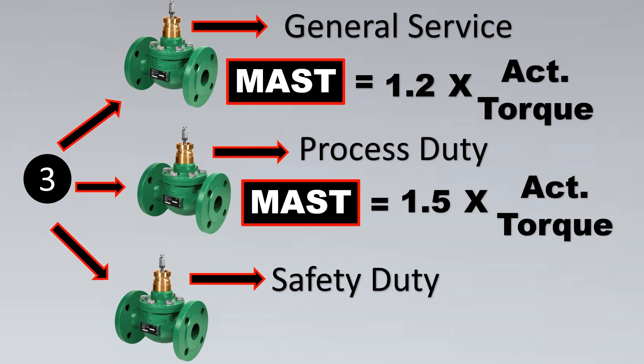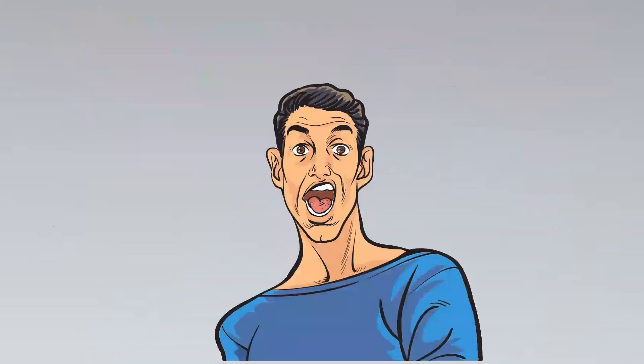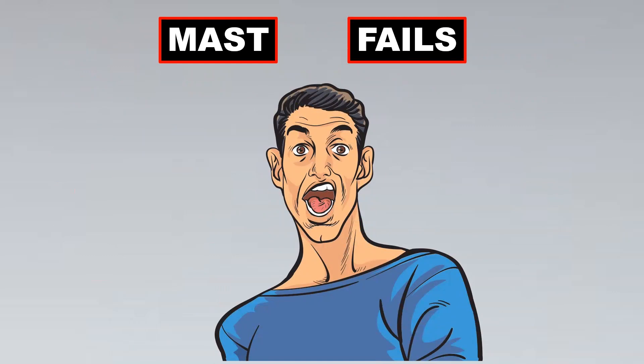When the valve is for safety duty applications — like shutting down the plant or preventing liquid escape — MAST should be equal to 2 times the actuator torque. These are the thumb rules to keep in mind while designing your on-off valve. And sometimes the safety factor can even go up to 2.5 times.